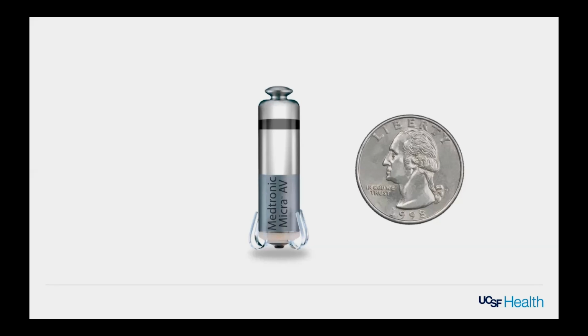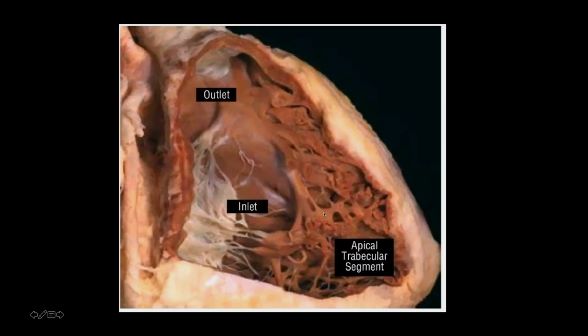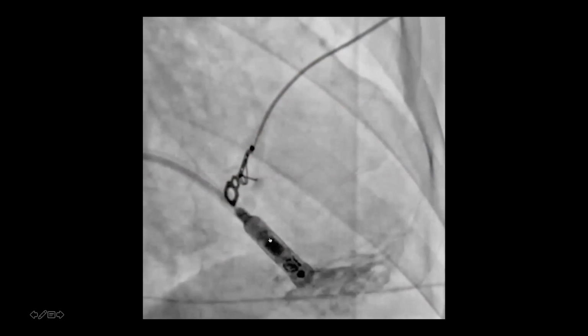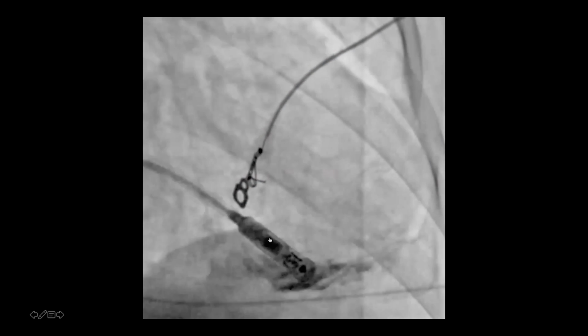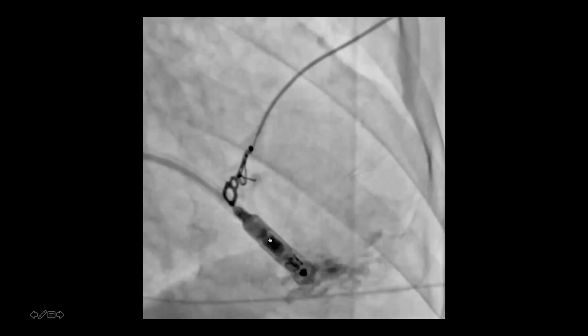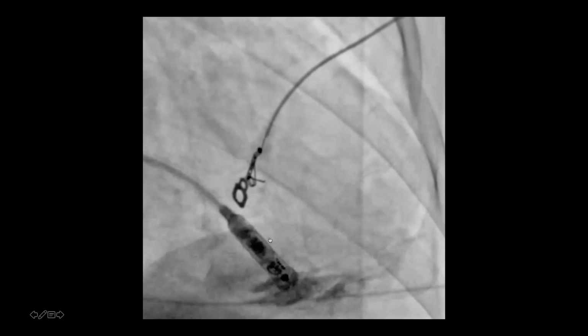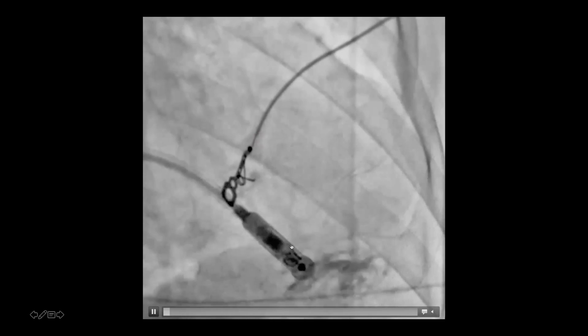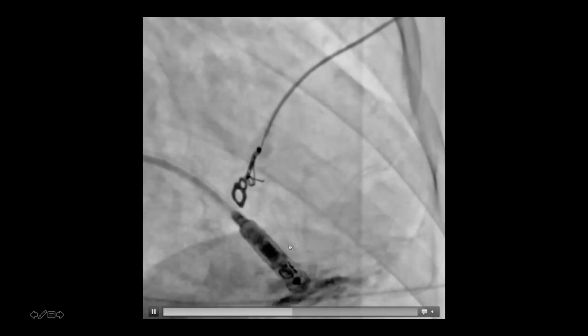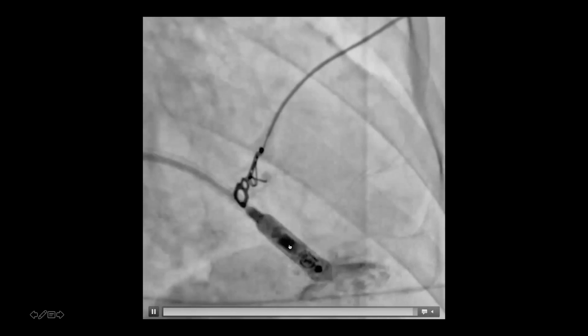It's a relatively small device, and it attaches to the inside of the heart using these tines right here. So the way we put this device in, we try to anchor the tines within this trabeculated septum section of the right ventricle along the septum. And the device is put in through a catheter that we insert through the groin, through the femoral vein in the leg. And we bring the catheter up to the heart. The catheter has the leadless pacemaker mounted in the tip. And then we inject some contrast to see, are we in a good spot?